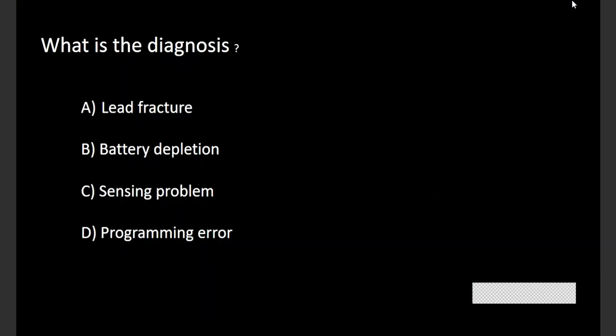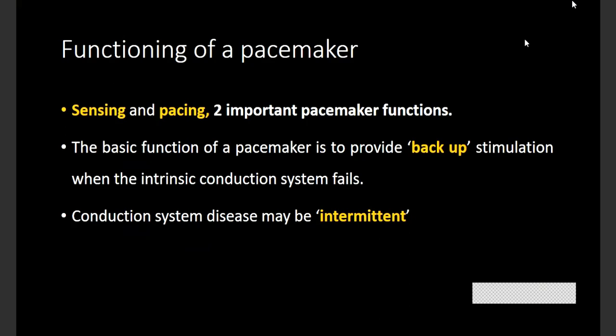Okay. So this is the basic functioning of a pacemaker. A pacemaker has two functions, not just one. Most of us think that the pacemaker's only function is to pace. That is wrong. A pacemaker does two things diligently. One, it senses every heartbeat, and second, it paces whenever required. That's very, very important. The function of a pacemaker is backup pacing.